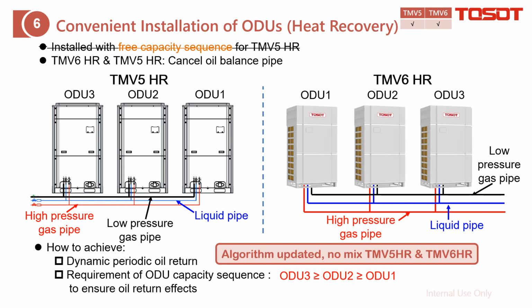As for the heat recovery system, this type is quite similar. As with GMV5 HR and GMV6 HR, there are 3 pipes, right? And for GMV6 HR, the oil balance pipe is also cancelled, and it also has this outdoor unit capacity sequence. It is the same.